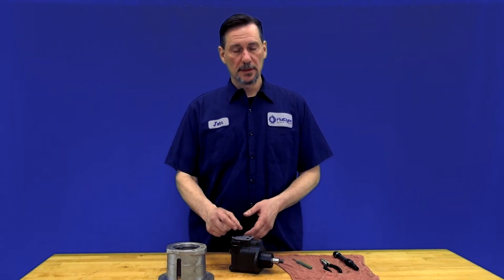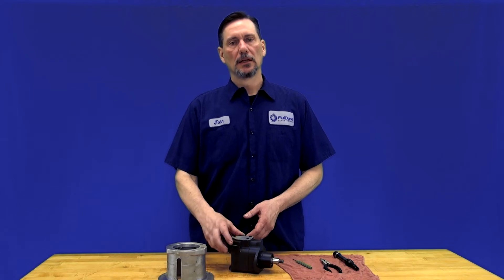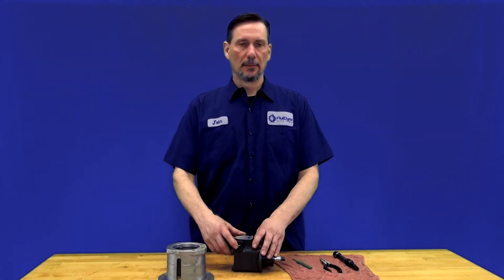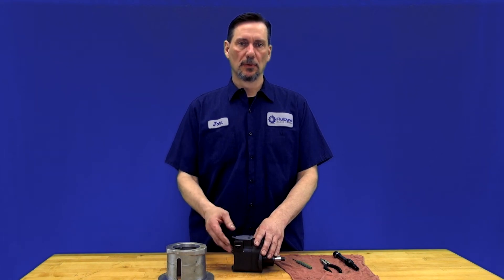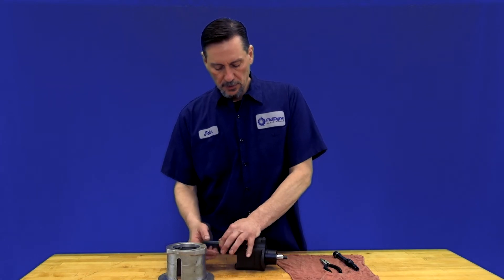It's relatively simple, but there is a fairly high spring tension behind this relief valve. So if you do have a worn-out o-ring around the plug on the side here, it might just pop out as soon as you remove the pin that's holding it in. What you want to do is get a punch and push through to remove this pin.